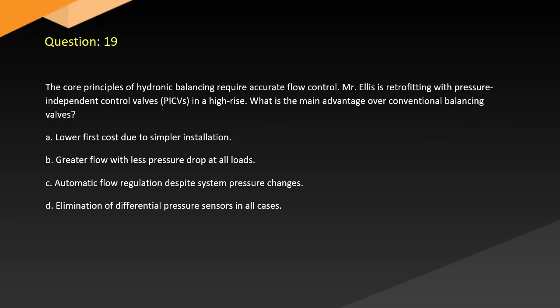Question 19. The core principles of hydronic balancing require accurate flow control. Mr. Ellis is retrofitting with pressure-independent control valves, PICVs, in a high-rise. What is the main advantage over conventional balancing valves? A. Low first cost due to simpler installation. B. Greater flow with less pressure drop at all loads. C. Automatic flow regulation despite system pressure changes. D. Elimination of differential pressure sensors in all cases.